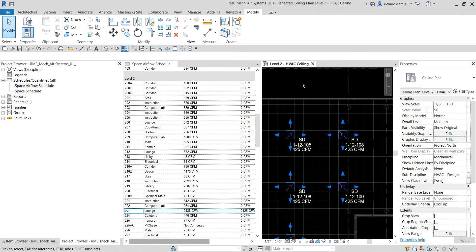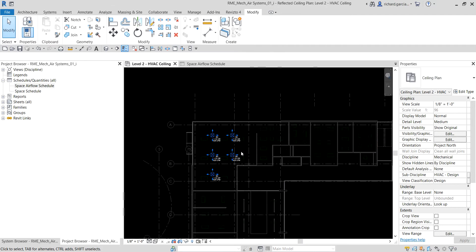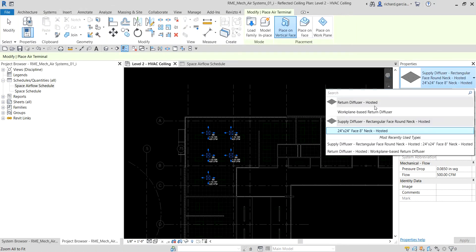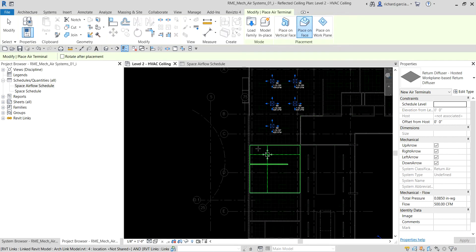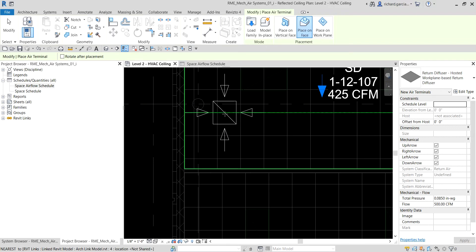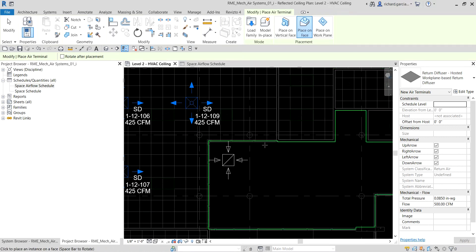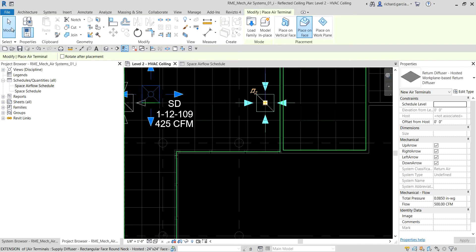Next, let's place a return diffuser. Maximize the ceiling plan — activate the Level 2 HVAC ceiling plan and tile views. Go to the Systems tab, click Air Terminal, and select the return diffuser hosted work plane family. Make sure 'Place on Face' is selected, then place your return diffuser on the ceiling.